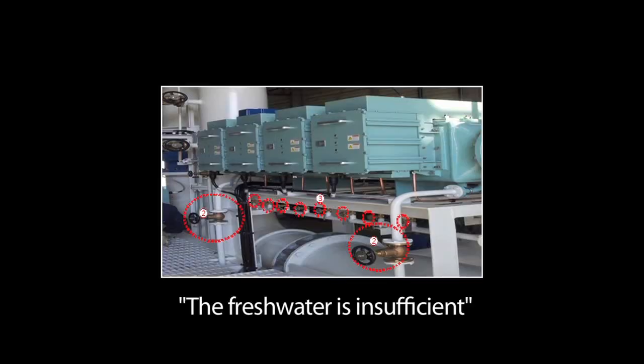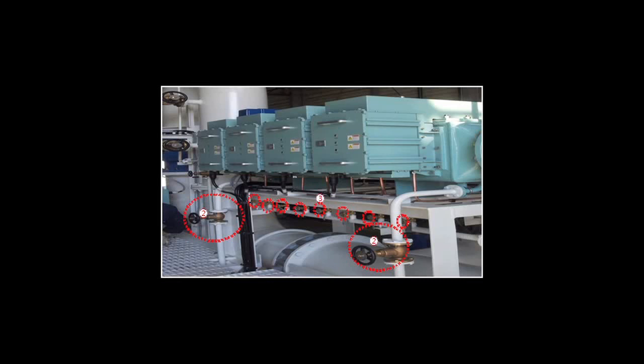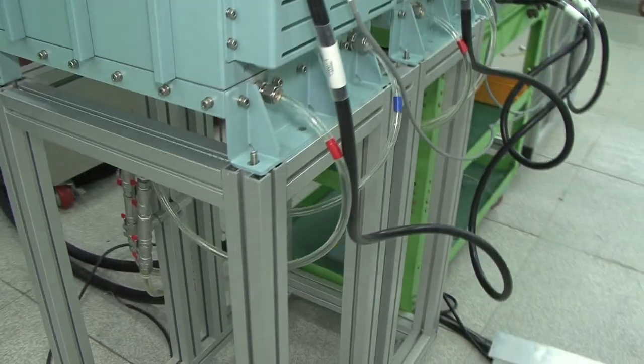6. FTU. Problem. ECS shuts down immediately after alarm message. The fresh water is insufficient appears. Reason. When cooling water level in FTU tank is lower than water level sensor. Solution. Need to provide sufficient cooling water to cool down PRU of ECU.